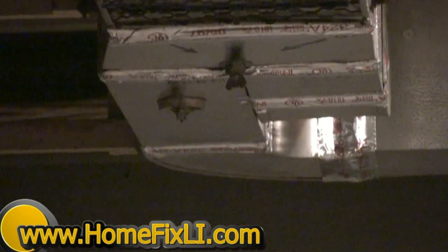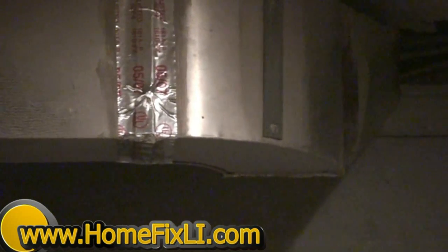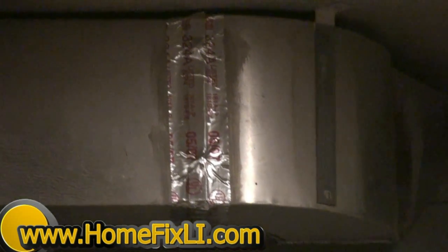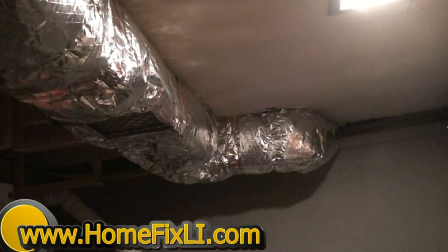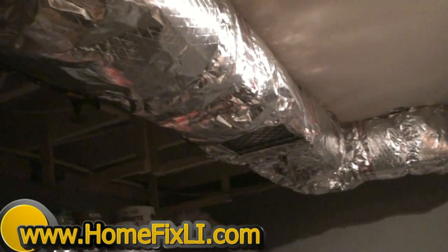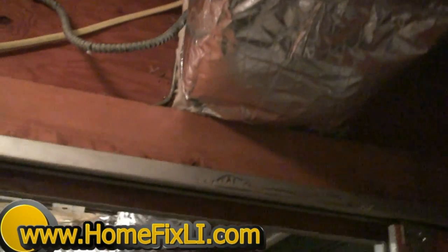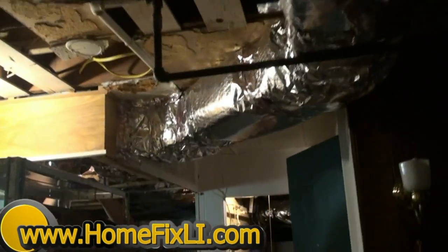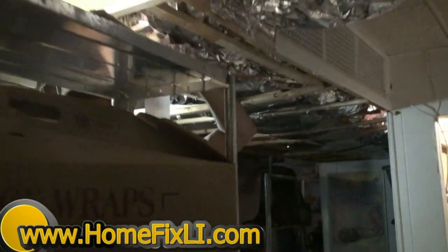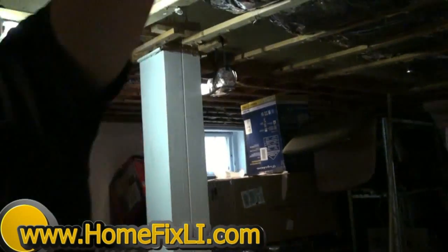Once all that's sealed up, then we want to go ahead and insulate all the ductwork, and for that we use an R6 foil-backed fiberglass duct wrap, and we want to make sure that we get as much of the duct as possible insulated in the unconditioned space. We don't want any heat leaking out. We want that heat delivered efficiently to where it's needed.